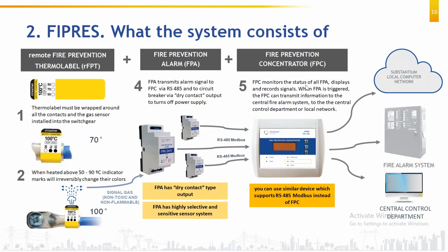And for detection of this gas, is the location of the FPA decided by your designer, or can it be installed anywhere within the cubicle? Because for 11 kV or 33 kV panels, distance clearance may be a major factor. Sir, when you install FPA in a particular panel, that clearance is definitely one of the main deciding factors. So as far as the functionality of the FPA and FIPRES goes, you can install it anywhere, as per functionality.